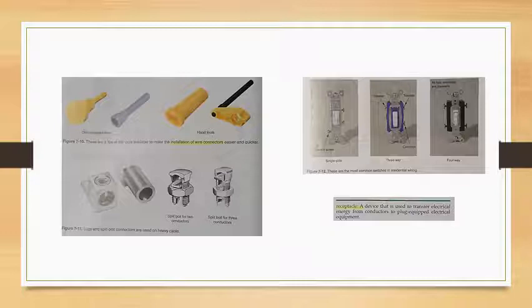A single pole switch has two terminals and controls a circuit from one position. When the single pole switch is in the on position, the two terminals are electrically connected. A three-way switch has three terminals and controls a circuit from two positions. One of the terminals is a color that is different from the other two. This is called the common terminal. The other two terminals are called travelers. A four-way switch has four terminals and controls a circuit from three or more positions. All of the terminals in a four-way switch are called travelers.